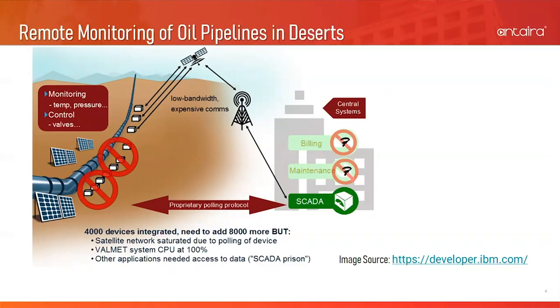The SCADA saw these timing gaps as error conditions because the polling and response didn't happen in a preset time interval. Secondly, it wasn't feasible to expand capacity by adding more devices. Since the SCADA was already connected to the existing 4,000 devices — pressure or temperature sensors or actuators mounted on the oil pipeline — when the SCADA tried polling all of these devices at once, the available bandwidth on the communication link between the satellite and the SCADA was saturated. The satellite networks were considered expensive and low bandwidth. Lastly, different departments such as billing or maintenance weren't able to check the status of the oil pipeline directly; they had to rely on the SCADA to do the job. All these challenges led to the creation of MQTT.